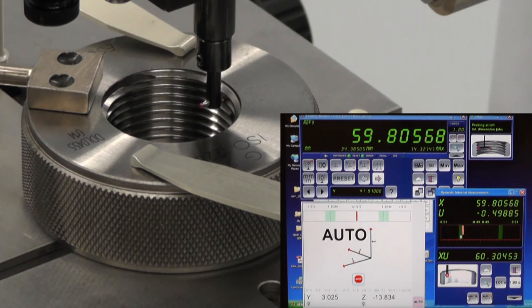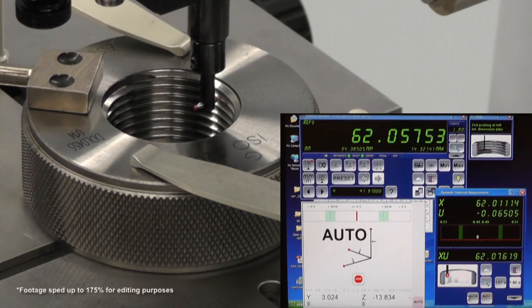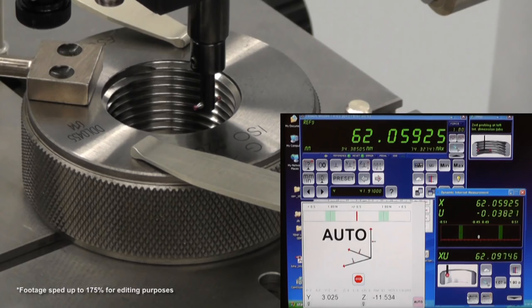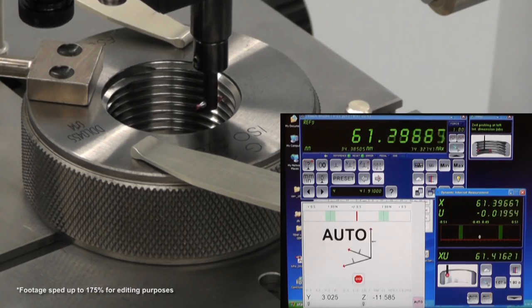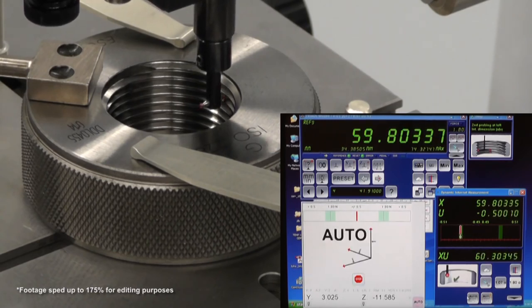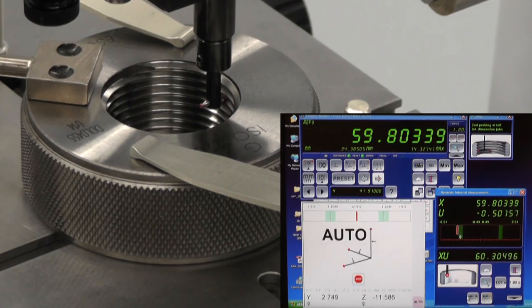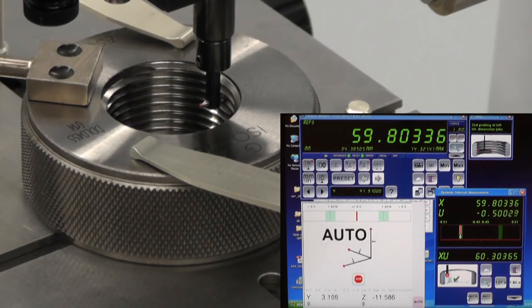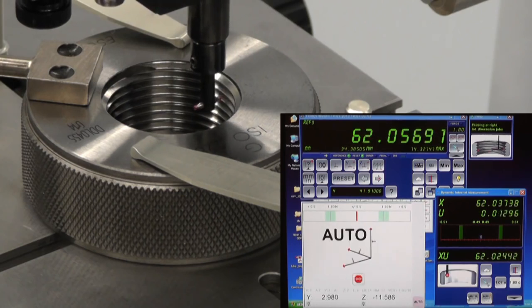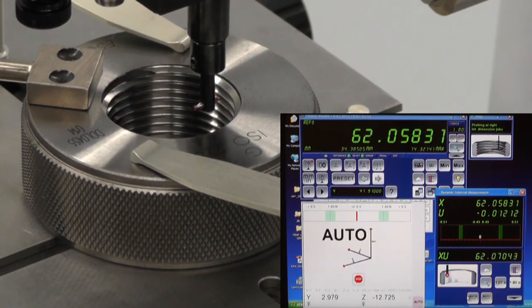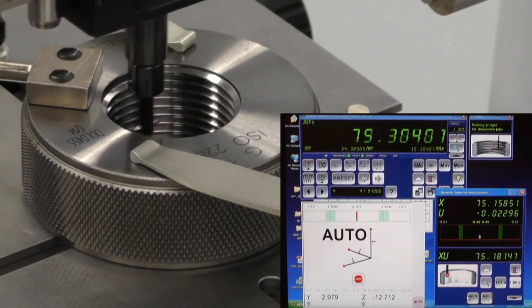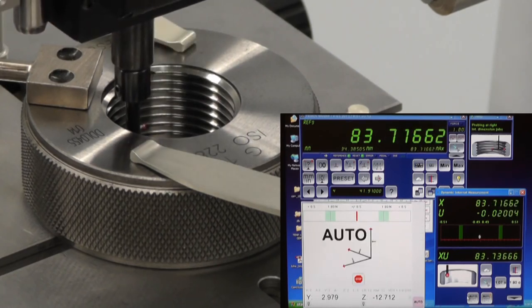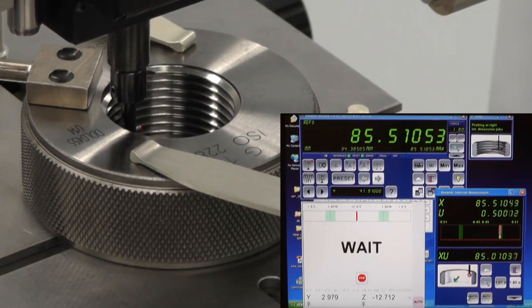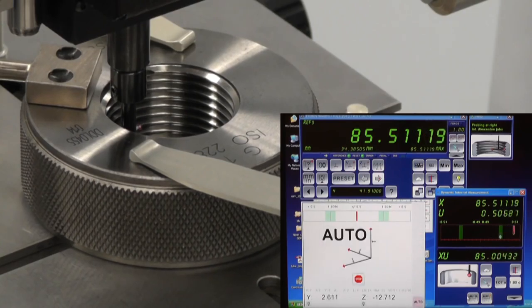The probe will sweep for a reversal point, then repeat the motion on the next thread down. To complete the measurement, this action is then performed on the opposing ring wall. This 3-point method can be used on straight or tapered thread rings.